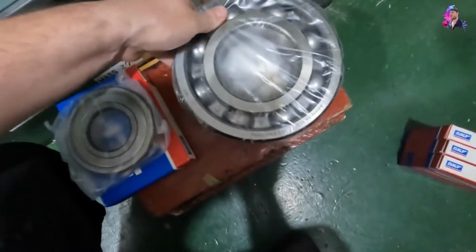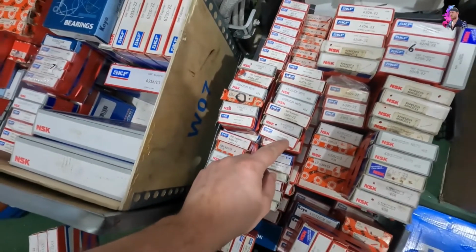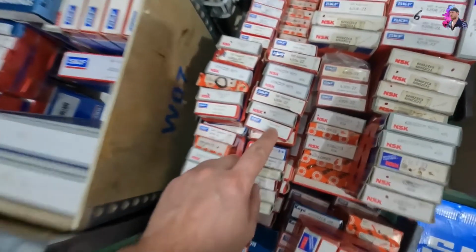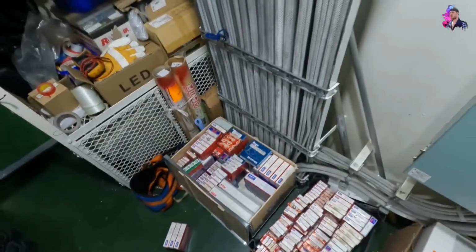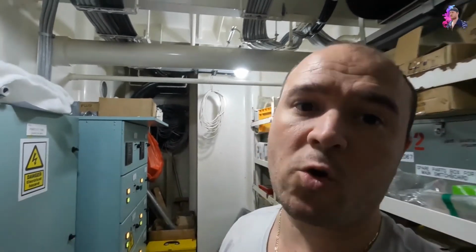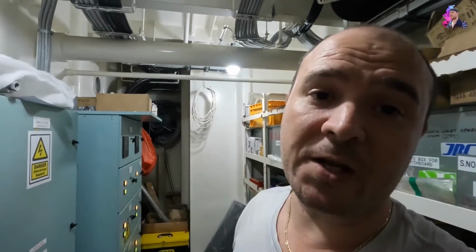I used a bigger motor just so you can see the code better, because I don't think this camera has a great zoom, and on a smaller bearing like this you could not see it on the camera. If you are faced with this situation, that is what you have to do. If there is no nameplate on the motor, then you have no choice, you have to open it and do a check like that. You have to check the number on the bearing.